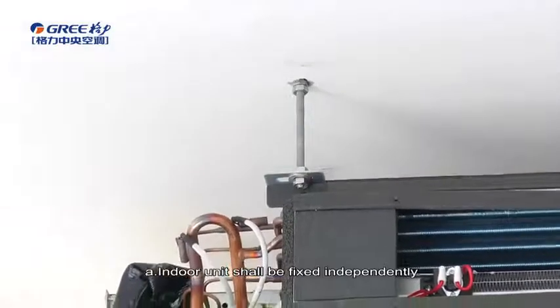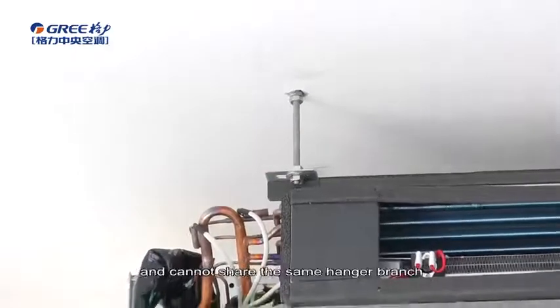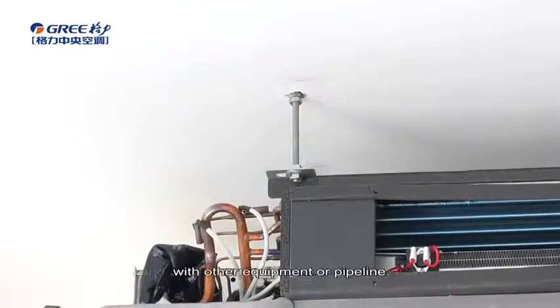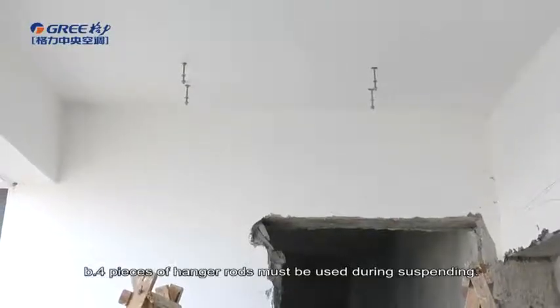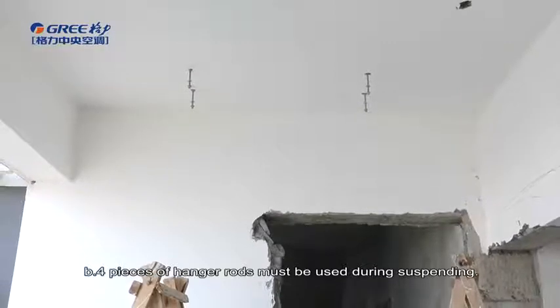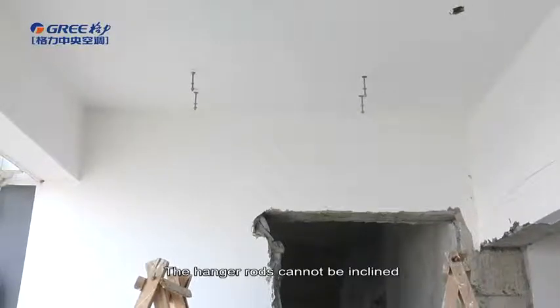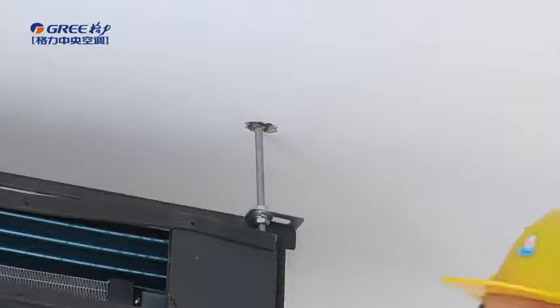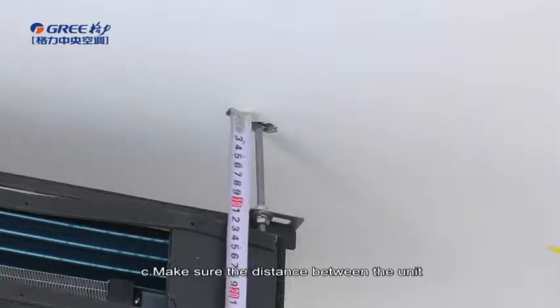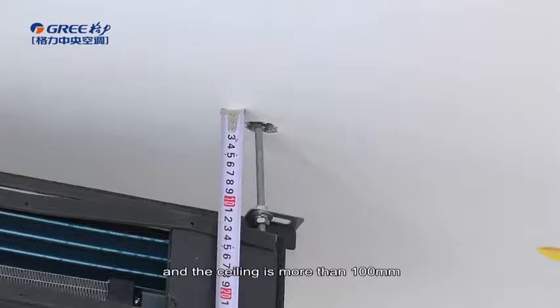A. Indoor units shall be fixed independently and cannot share the same hanger branch with other equipment or pipeline. B. 4 pieces of hanger rod must be used during suspending. The hanger rods cannot be inclined after finishing installation of unit. C. Make sure the distance between the unit and the ceiling is more than 100 mm during installing indoor unit.